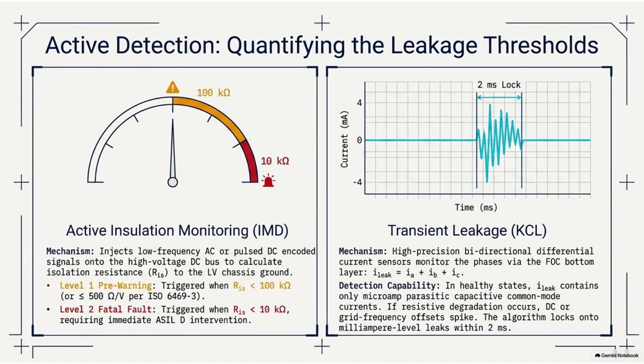The previous sensors, the IMD and the KCL monitor, are reactive. Right. They catch the leak as it happens. Exactly. They catch the failure as it begins. Yeah. The zero-sequence algorithm is predictive. It analyzes the resonant frequency of the high-frequency currents in the system.